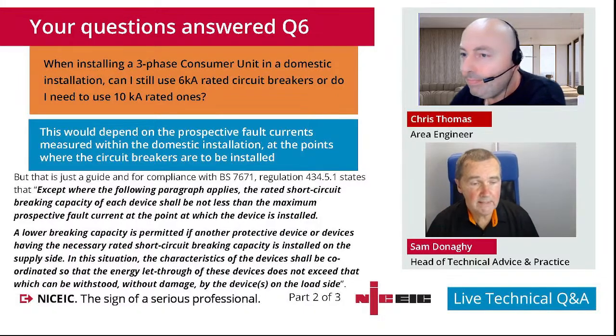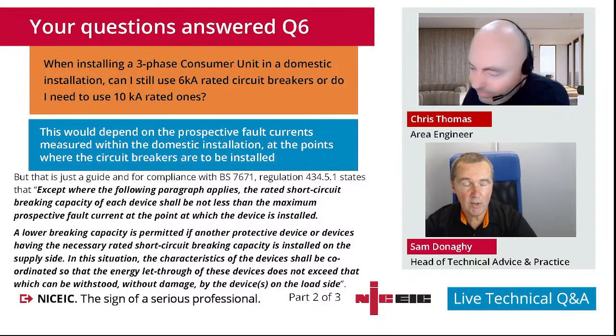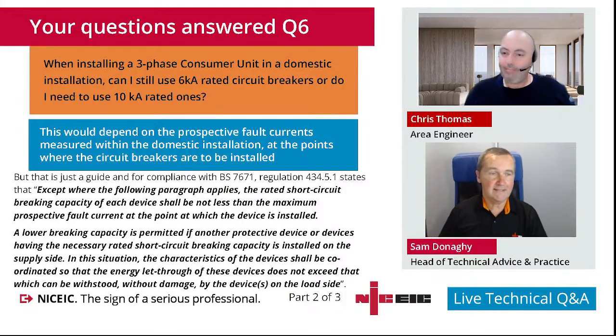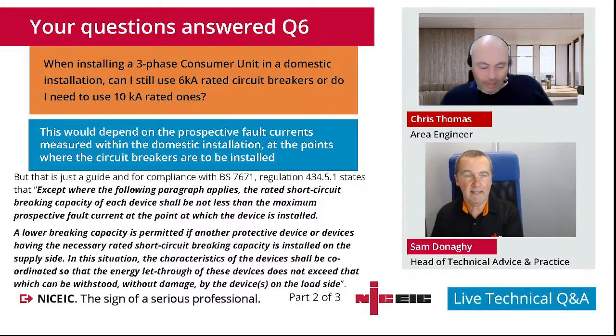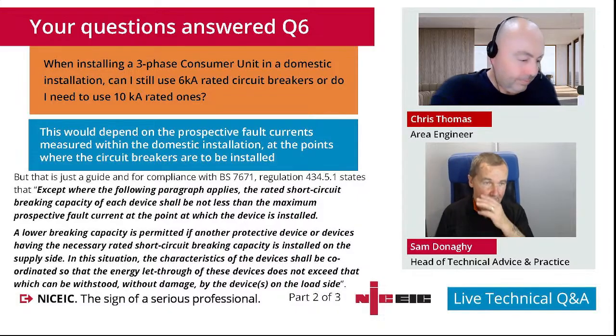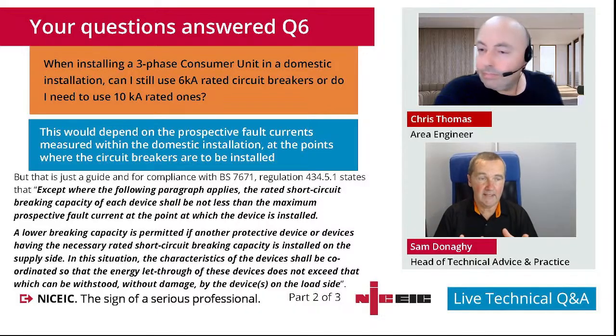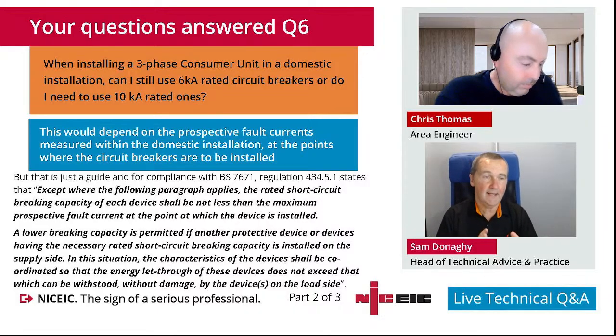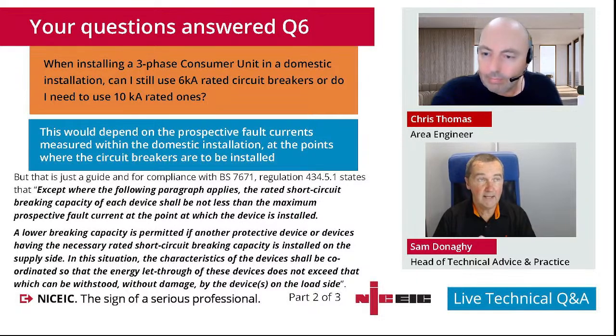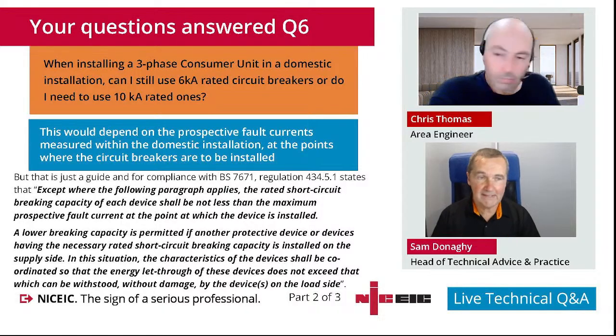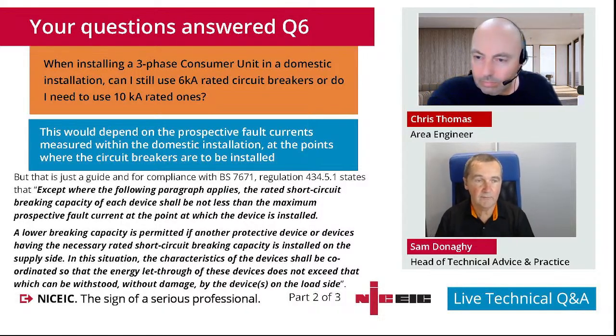Yeah. So I think it's one of those things where perhaps sometimes we're misguided by familiarity, because we're used to domestic single phase installations having 6 kA rated breakers, and industrial or large commercial three-phase distribution boards having 10 kA rated, and it's really nothing to do with whether it's single phase or three phase, or whether it's domestic or industrial.